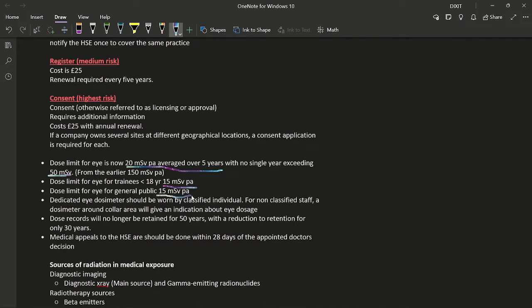The dose limit for the eye for the general public is also 15 millisieverts per annum. A dedicated eye dosimeter should be worn by classified individuals; for a non-classified individual, a dosimeter around the collar area will give an indication of eye dosage. Dose records will no longer be retained for 50 years — they will be stored for only 30 years. Medical appeals to the HSE should be made within 28 days of the appointed doctor's decision.